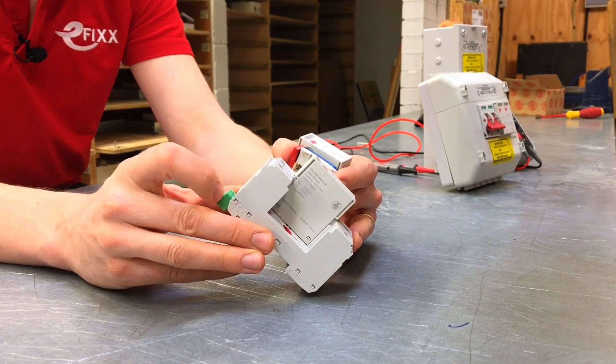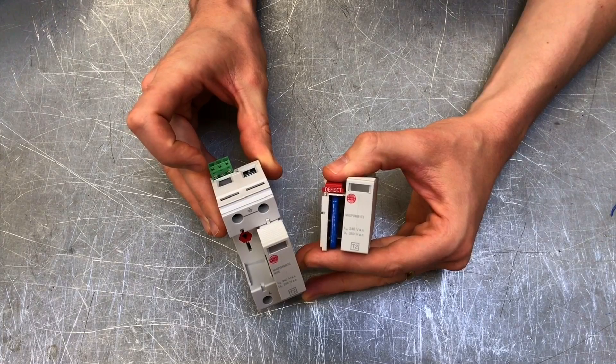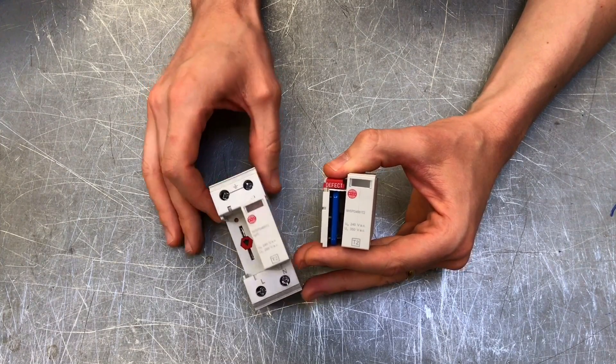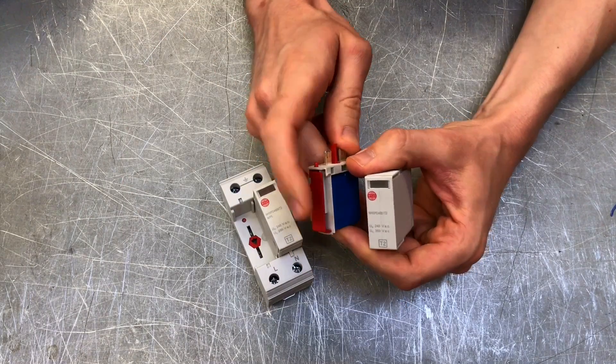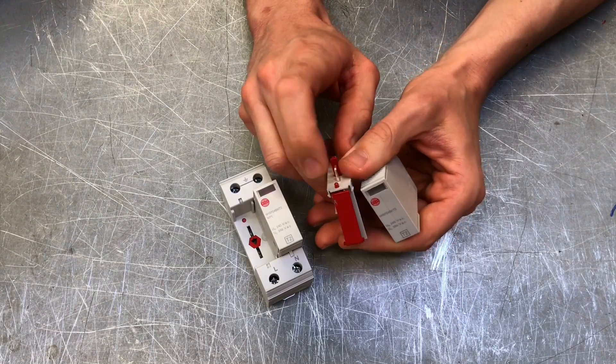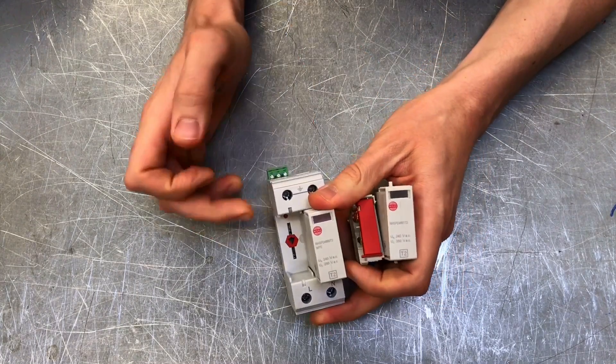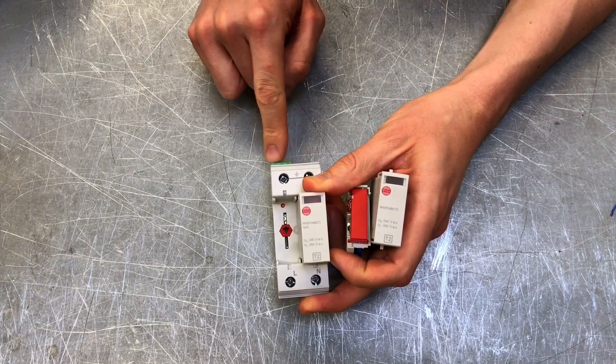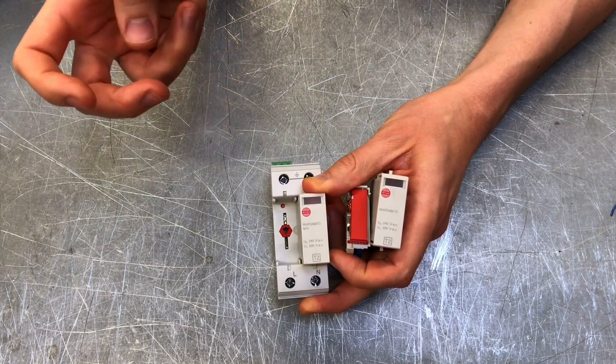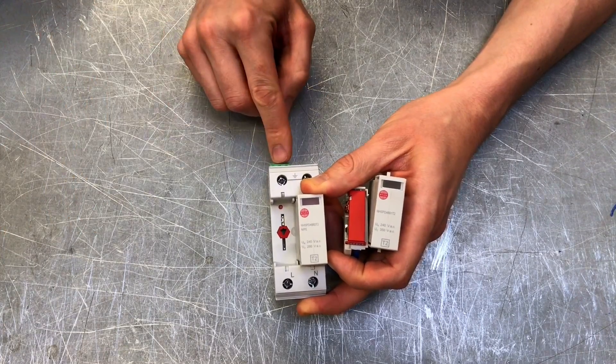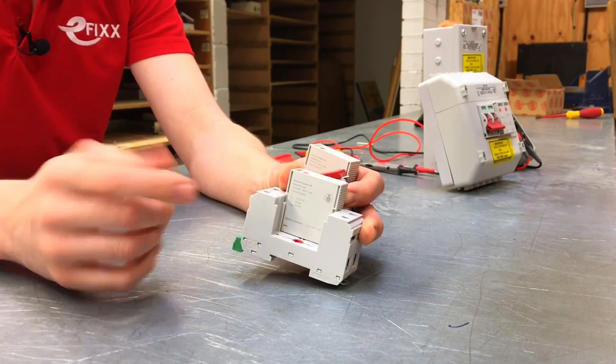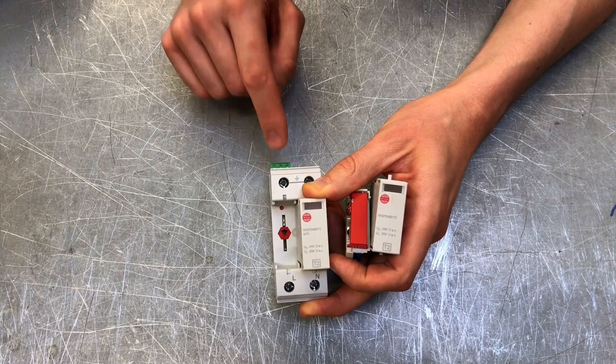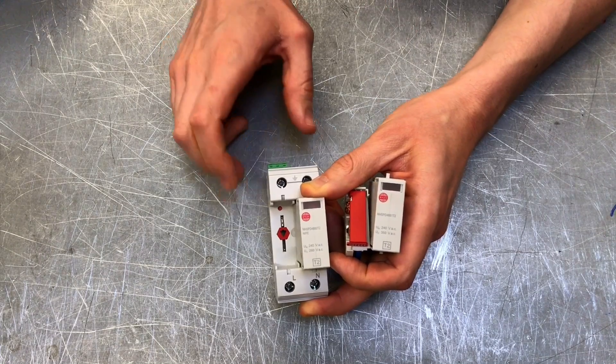That is possible because we've got on top of our surge protection device here an auxiliary contact. We can feed a signaling circuit through that. When this reaches end of life and springs forward, this little nib on the back will also shoot in and no longer push down on this tiny red dot you can see in the back. When that happens, it operates a micro switch which will send a signal through here to maybe a remote indicator, a lamp on a panel board, maybe an audible signal, or even into a SCADA system.